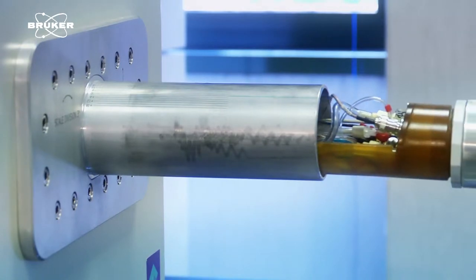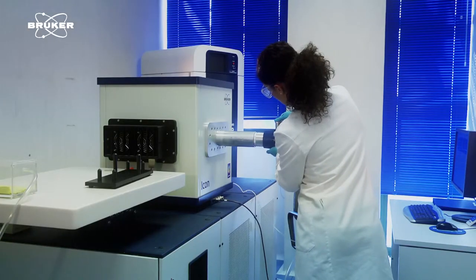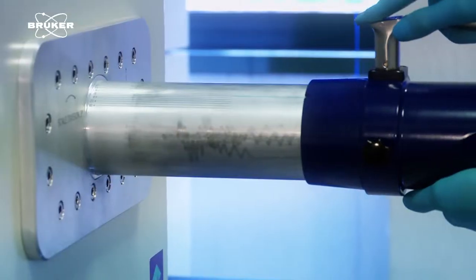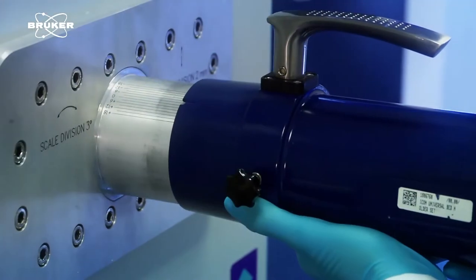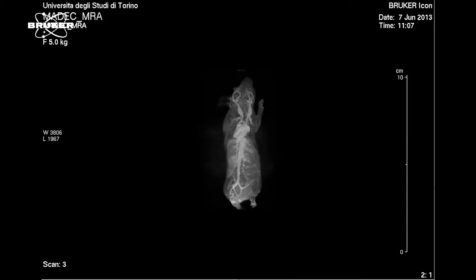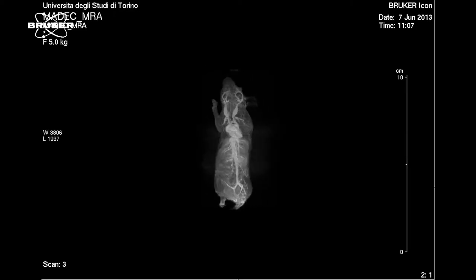There are reference scales to choose the right orientation to affix the animal support to the magnet. This is all the setup that is needed. The respiratory pillow is connected to a monitoring and triggering device which is connected to the system.